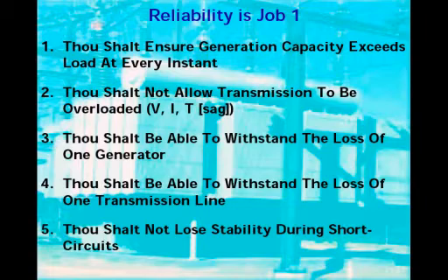They're responsible for making sure that load is always met, or that the supply of electricity meets the demand of the consumer. And so first of all, they have to make sure they have enough generation capacity at the ready. Furthermore, that power will not help all the people if it can't get to them. So they have to make sure none of the lines are overloaded. That is, when the current gets too big, you have too much resistive loss and heat that will cause the lines to sag. We don't let that happen.